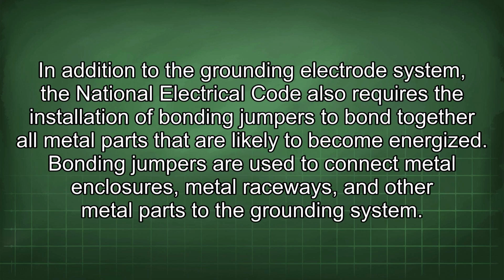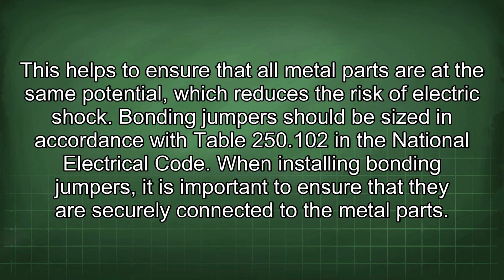In addition to the grounding electrode system, the National Electrical Code also requires the installation of bonding jumpers to bond together all metal parts that are likely to become energized. Bonding jumpers are used to connect metal enclosures, metal raceways, and other metal parts to the grounding system. This helps to ensure that all metal parts are at the same potential, which reduces the risk of electric shock. Bonding jumpers should be sized in accordance with Table 250.102 in the National Electrical Code.